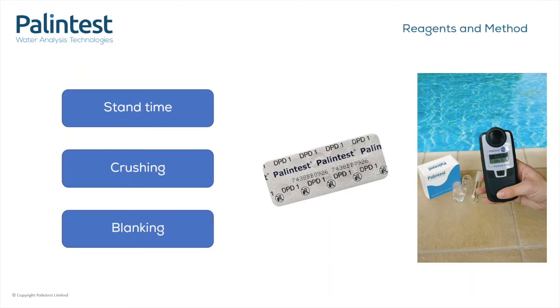A final thing that we need to consider when doing a test is the blank. The blank needs to be your sample without any reagents added, in a clean test tube. This is used to tell the instrument what the sample looked like before you added the reagents, so it knows how much adding the reagents has changed the percent T value and what effect that colour change has had. It's important to do the blank with each sample you do to get the best results.